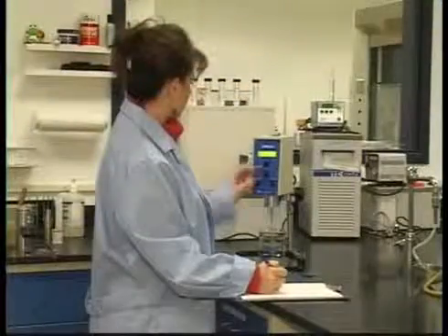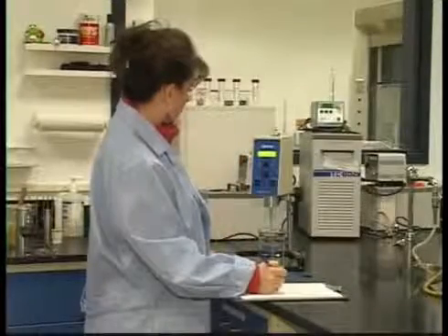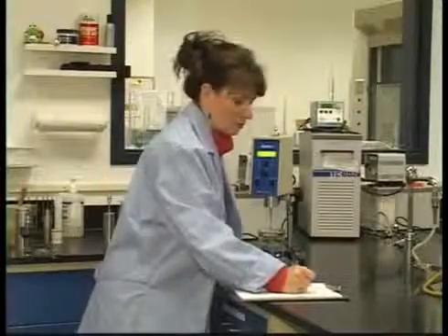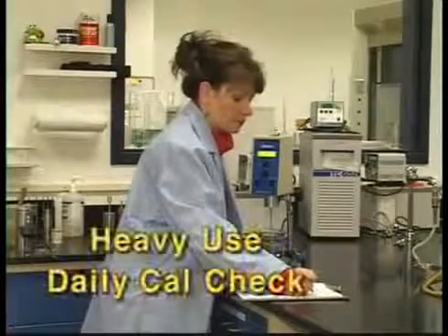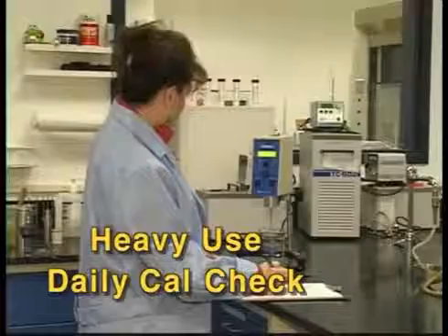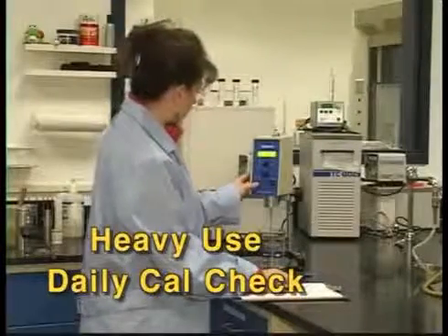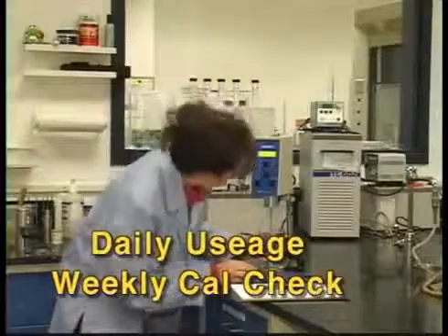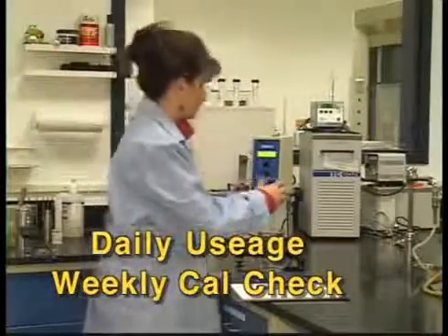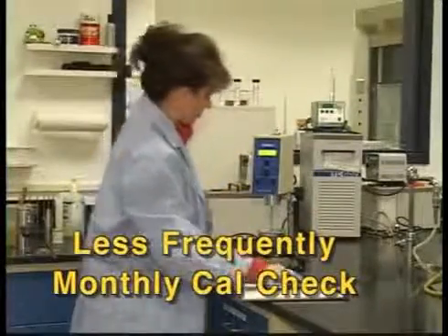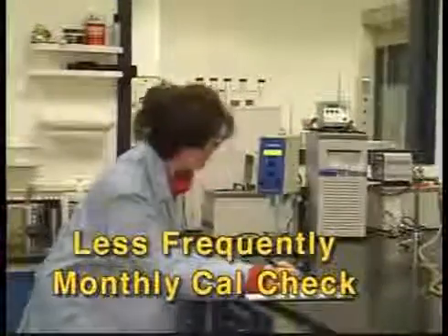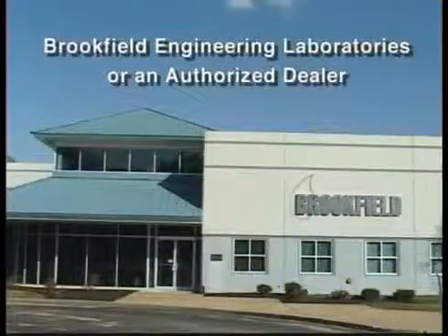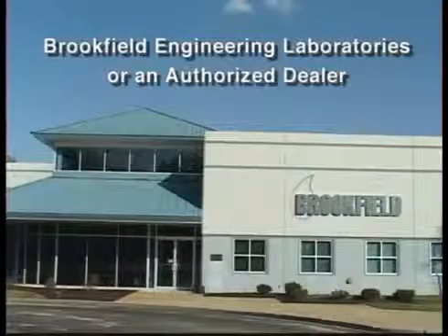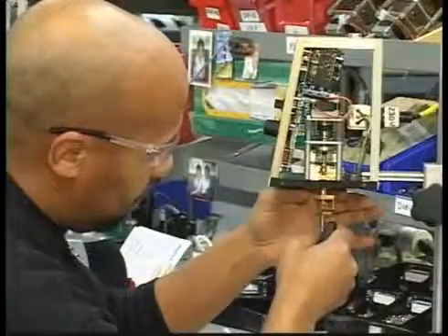A common question is how often should a calibration check be run? The answer really depends on how often the instrument is used. For example, if an instrument is being heavily used, say on multiple shifts, a daily calibration check is best practice to ensure accuracy. Daily usage, 5 days a week, may require a calibration check be performed at least once a week. For instruments used less frequently, perhaps once a month or once every few months will be fine. But to ensure the health of your instrument for many years, return this to Brookfield or an authorized dealer once a year for a full calibration, certification, and cleaning.